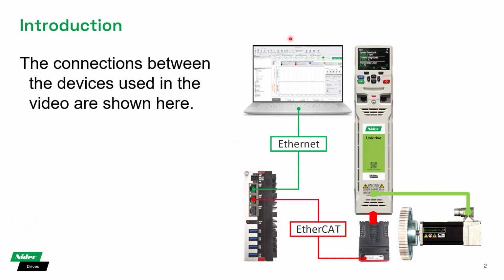In this video, I've got a laptop running the TwinCAT software, with an Ethernet connection from my PC to my chosen hardware, in this case an IPC, a C6025 IPC. These steps work essentially the same regardless of hardware, whether it's a PLC or controller. I've then got an EtherCAT connection from my IPC through to my drive's EtherCAT interface, an SI EtherCAT, plugged into my drive, a UniDrive M700. The steps are identical if using a drive from our Digitax HD range, such as a Digitax HD M753, which already has a built-in EtherCAT interface.